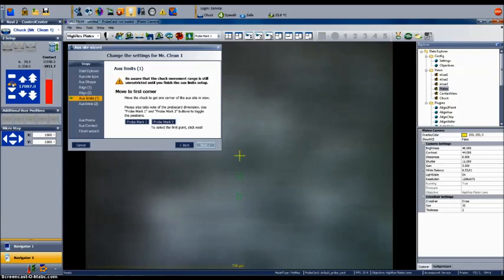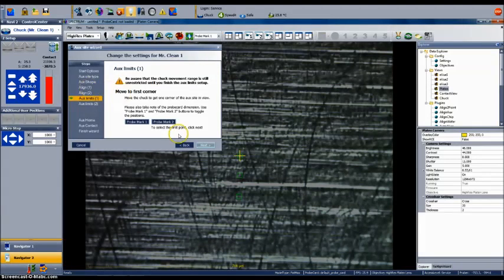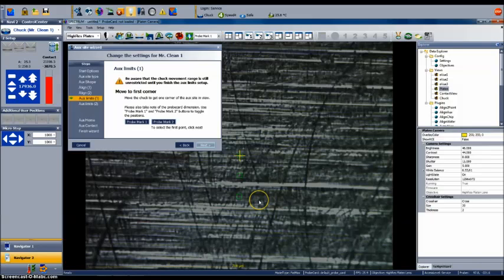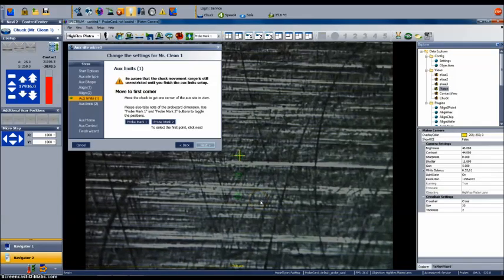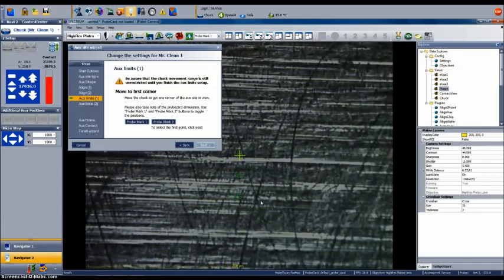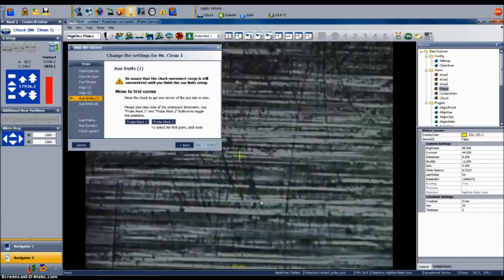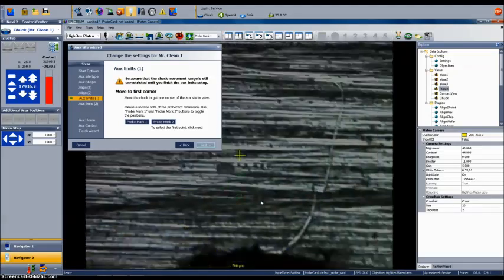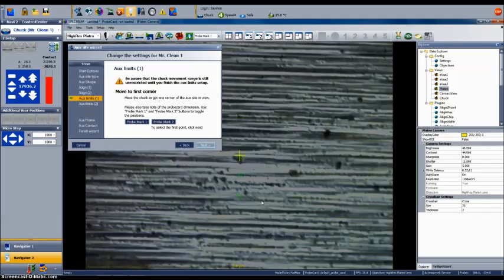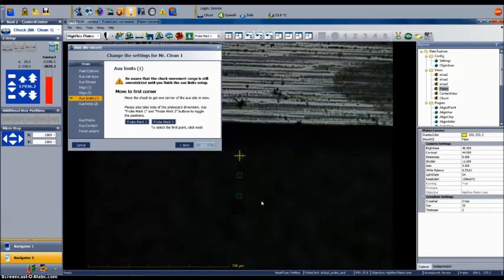To set the aux limit 1 position, first you will need to adjust focus to obtain a clear image. For safety, I always move the chuck in the downward Z direction first before moving up in Z to obtain good focus. Then move the chuck to the first alignment position using the joystick. At this point in the wizard, all software fences have been removed and stage movement is unrestricted. First, locate the cleaning pad surface, and then find the lower left corner of the pad using the joystick.